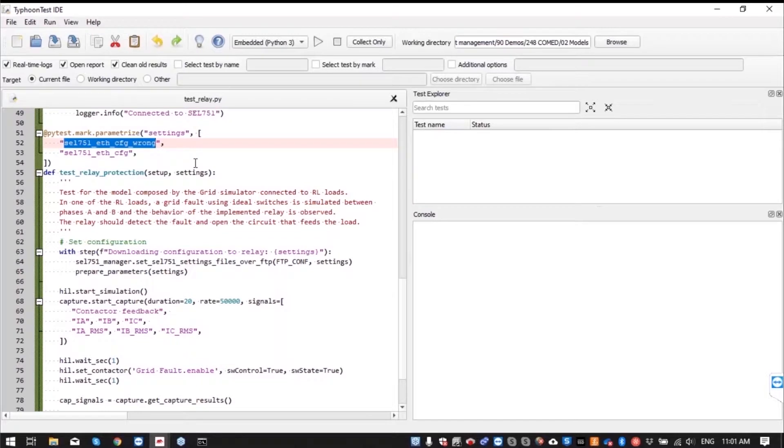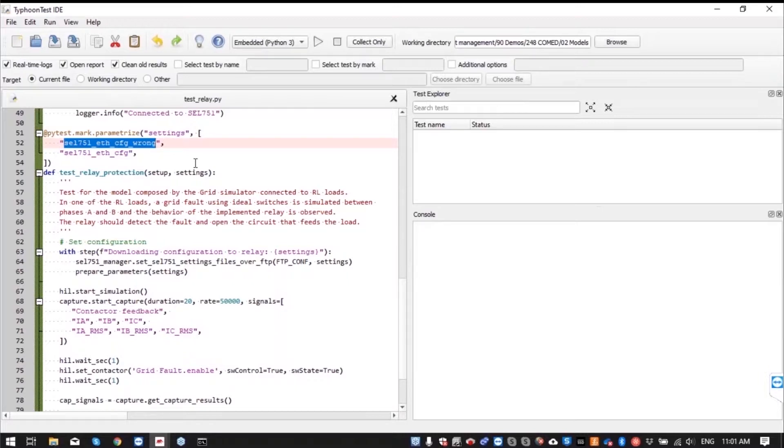The first one that we call wrong has the wrong value of current for the short circuit protection. Meaning it would be too high so when the short circuit kicks in it's not going to detect it and it's going to leave the circuit connected.